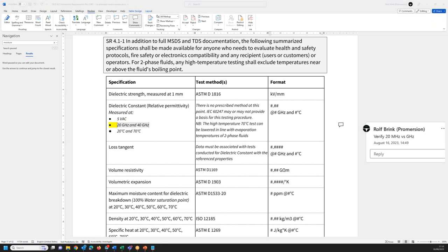This is Arad from the signal integrity workstream. Basically you do a range of the spectrum to 40 GHz, but at lower frequency it depends on the fluid - if the dielectric constant stays constant across the frequency range then it shouldn't be a problem technically, because it wouldn't change. But in some fluids, for instance some Novec two-phase fluids, at lower frequency range the dielectric constant is higher, then at higher frequency range it will drop. Whether low-frequency testing would have an effect on anything - that's the part I don't know.